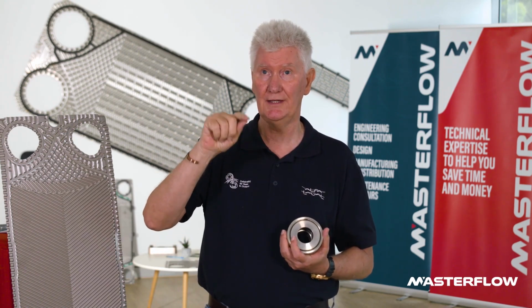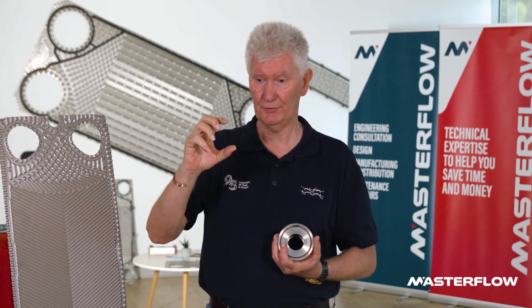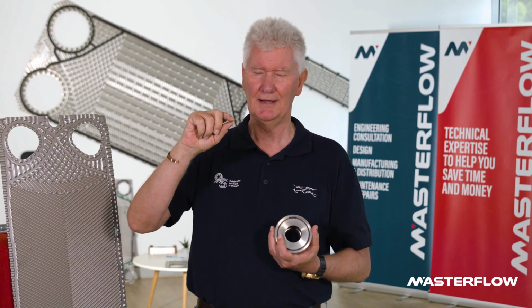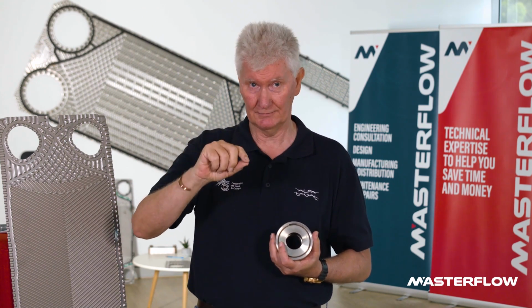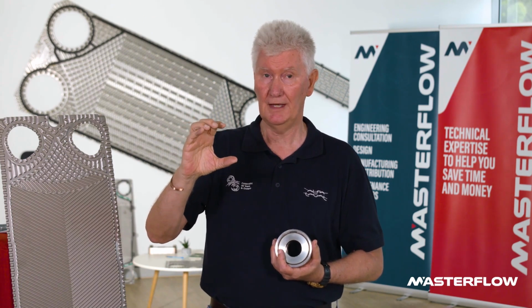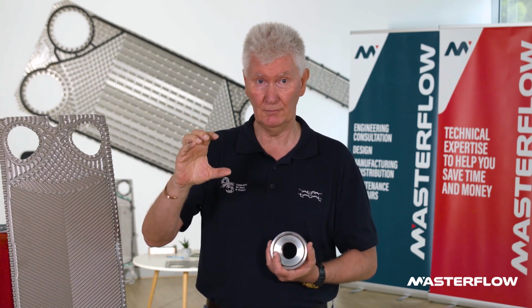The philosophy Alfa Laval uses in designing the frames is to use as few bolts as possible, but of a bigger diameter. In the pressure vessel calculation, you have to reach a certain bolt area, and we achieve that with large diameter bolts, M39 in the norm, and M48 for high pressure. They're rolled thread bolts, not cut thread, which makes them stronger, with increased diameters.